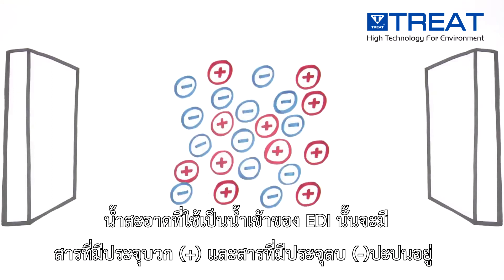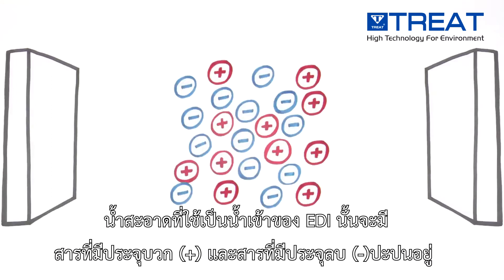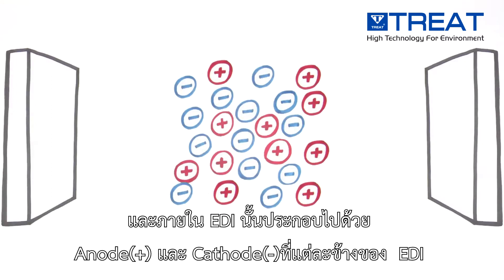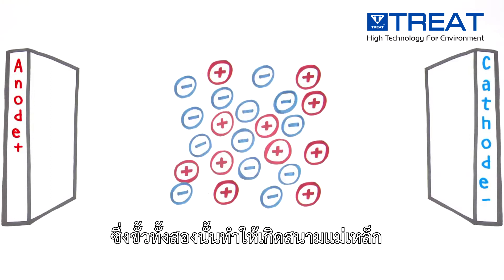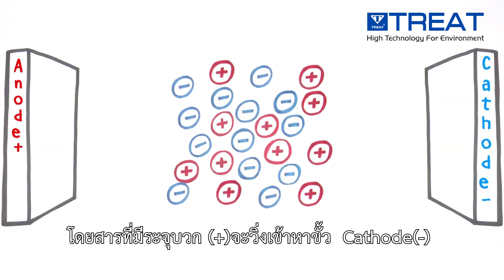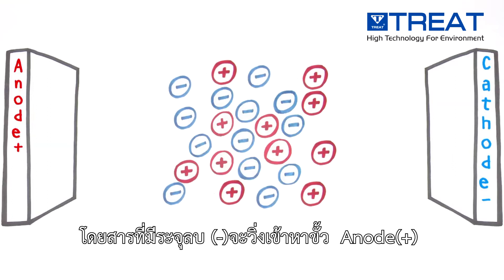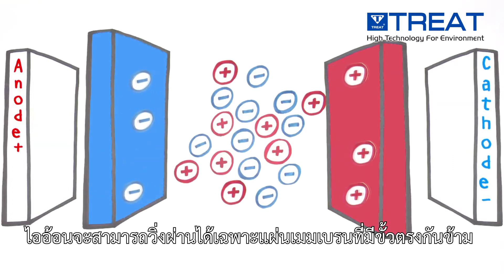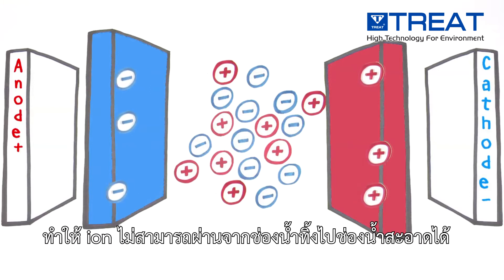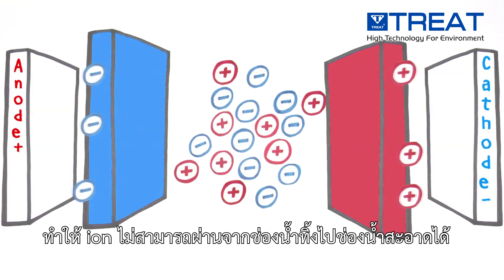Pre-treated water containing positively and negatively charged ions flows into CEDI modules constructed with an anode on one end and a cathode on the other end to provide an electric field. Opposites attract, so positive ions move toward the cathode and negative ions toward the anode. Ions can only pass through an oppositely charged membrane, so the alternating cation-selective and anion-selective membranes trap the ions.